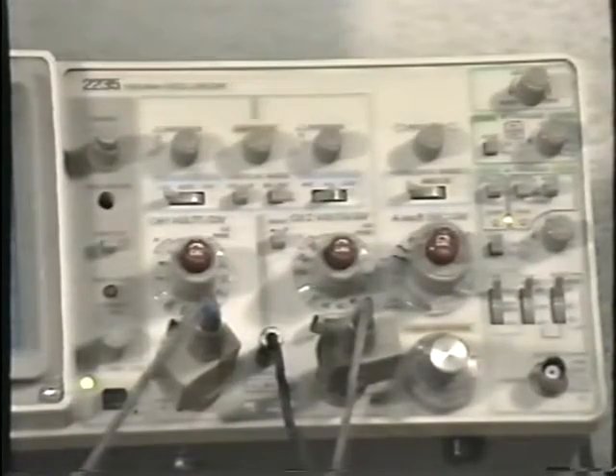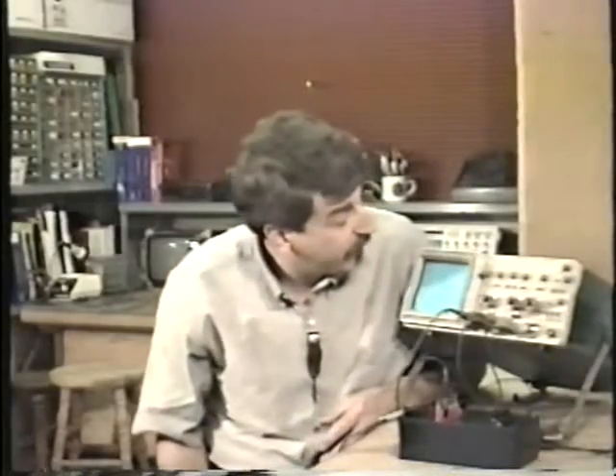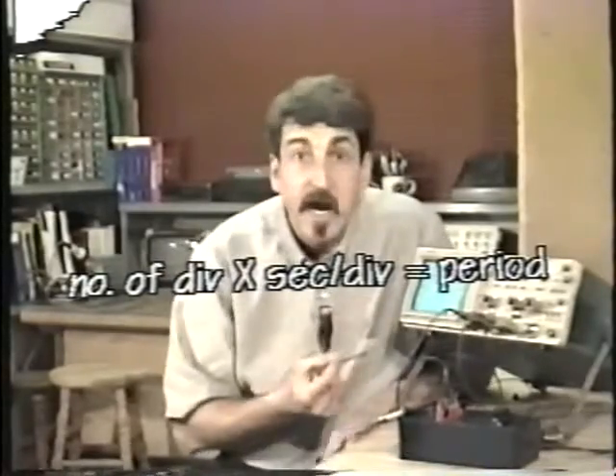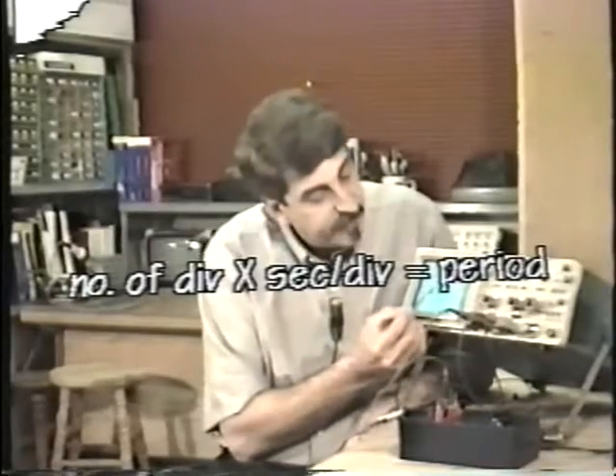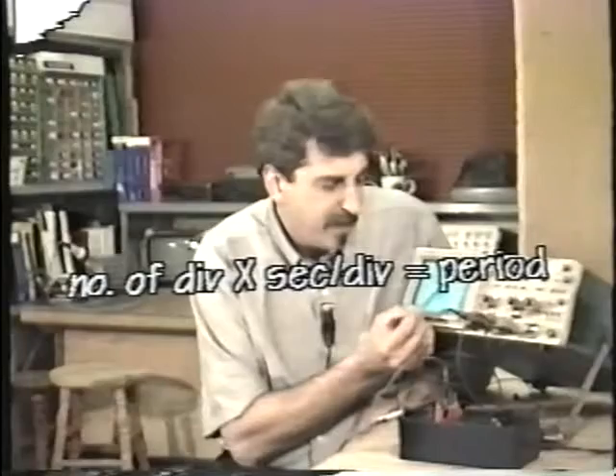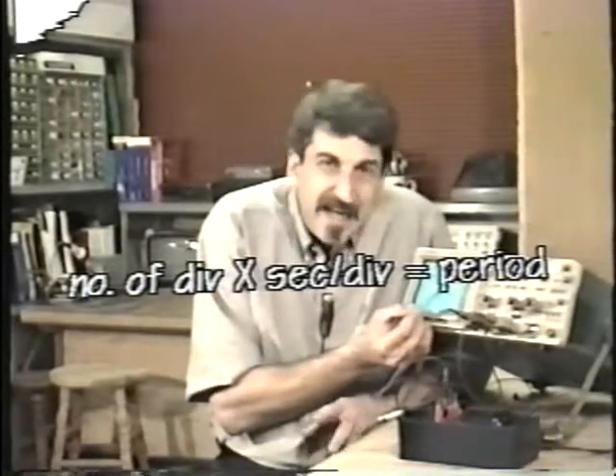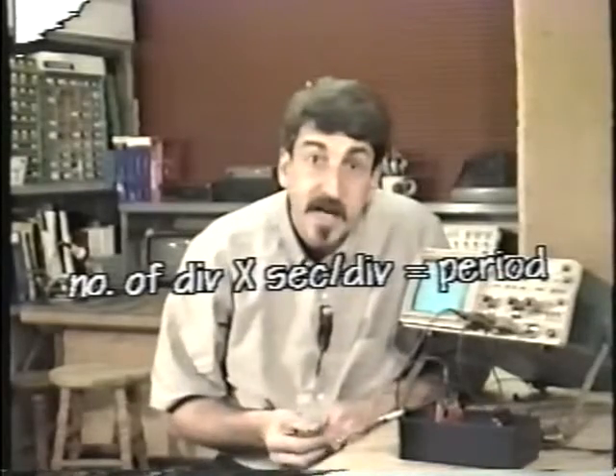Well, we need to go over here and look at the seconds per division control and see where that's set. At the moment, it's set on 5 milliseconds per division. That's 5 thousandths of a second per division. We have about 3.2, 3.4 divisions there times 5 milliseconds per division. Instead of doing the math, the easiest thing is to simply count it out. It's on 5 milliseconds per division, so here's 5, 10, 15, maybe 16 and a half or 16 and 3/4 milliseconds, something like that.